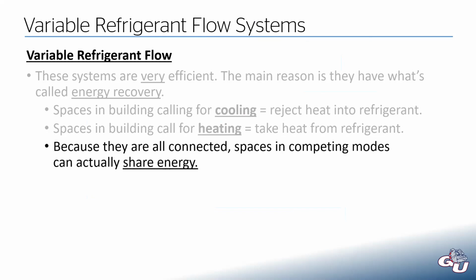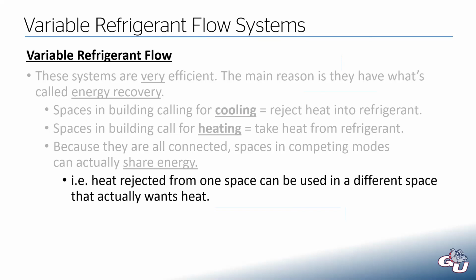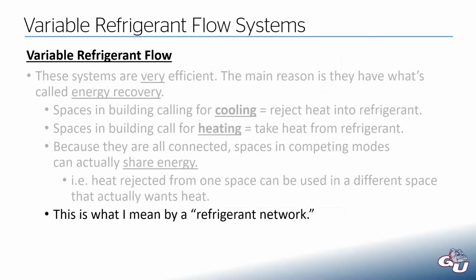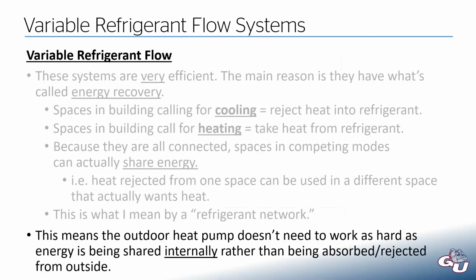Because in a VRF system, all of our fan coils are connected to one common network. What this means is that when you have these rooms and these fan coils that are in competing modes, so some in heating, some in cooling, they can actually share energy. So if you're taking heat out of one space, you can then use that heat in a different space that actually wants that heat energy. And so that's where I come up with this term of refrigerant network. All of these rooms are communicating to each other. And ultimately, this means that the heat pump outside doesn't have to work as hard because now we're sharing energy internally. We're just moving energy around the building rather than having to reject a bunch of heat outside and absorb a bunch of heat outside.